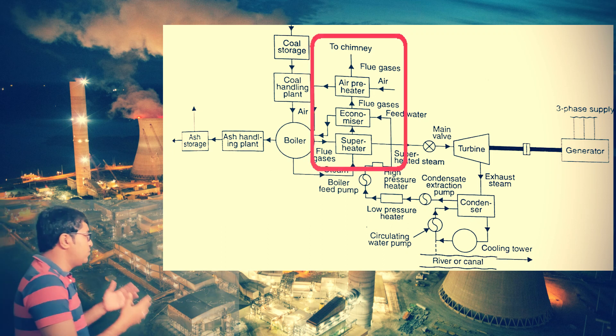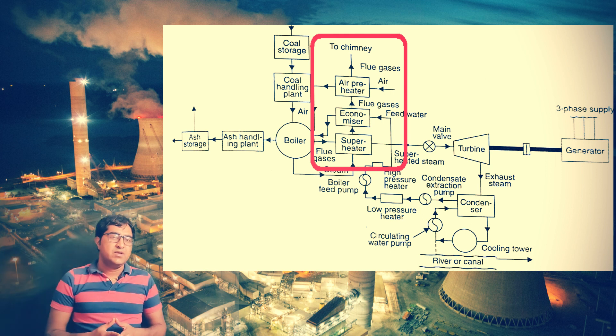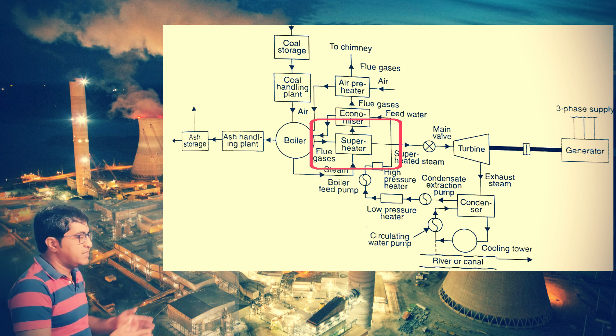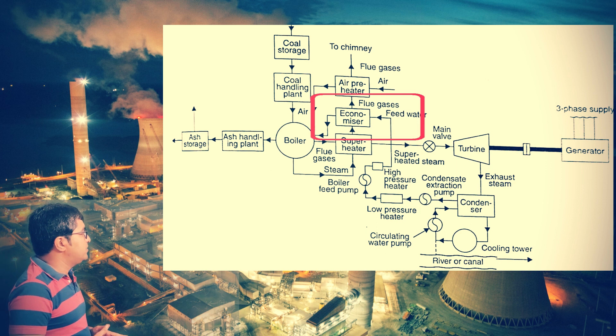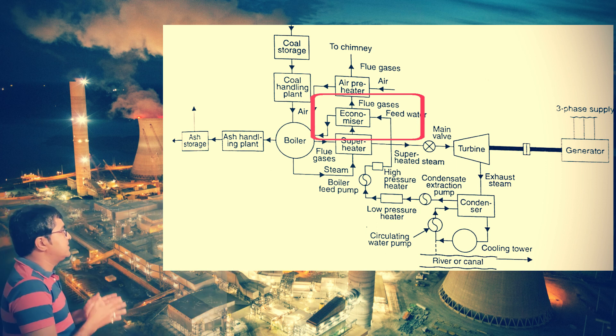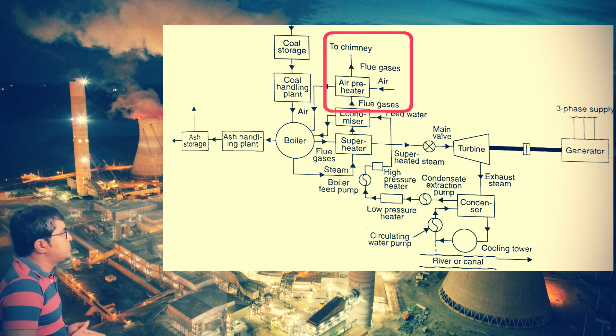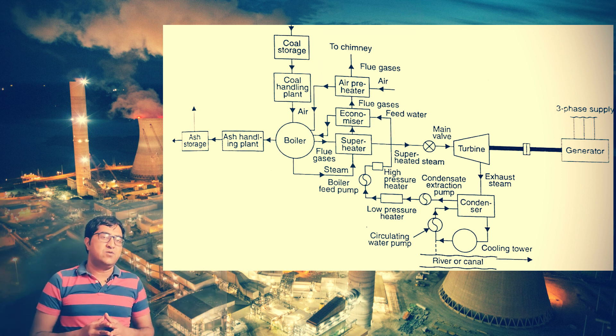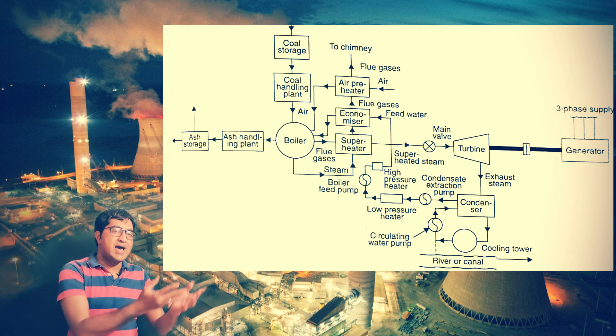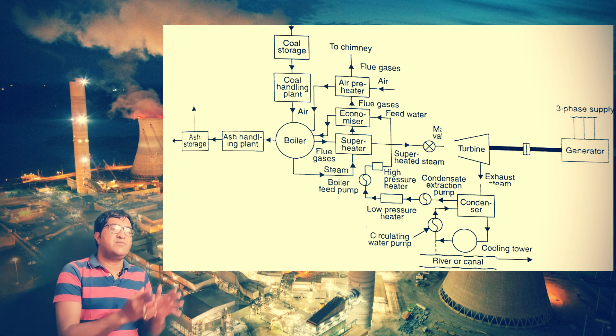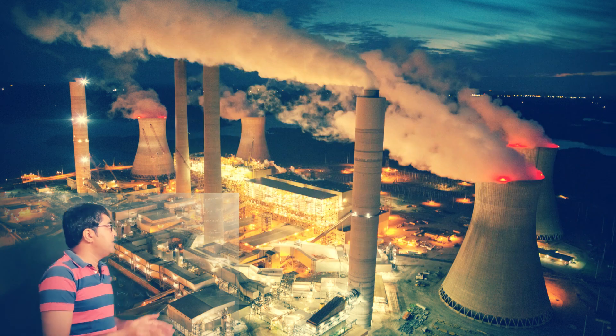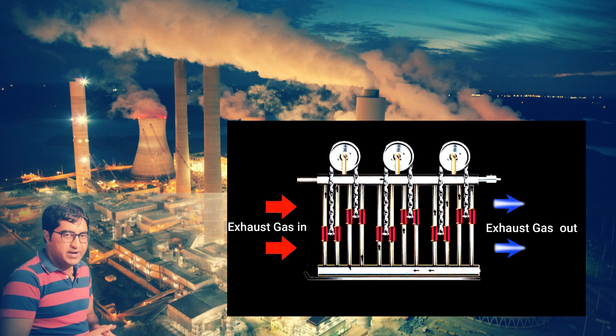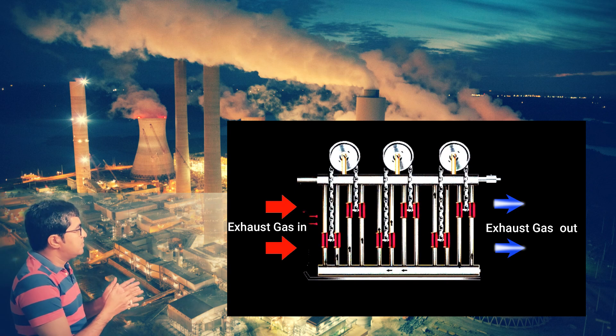The flue gases generated in the boiler pass through the superheater, where they transfer heat to generate superheated steam. Then the flue gases pass through the economizer, and finally through the air preheater before being exhausted to the atmosphere via the chimney. Since a small amount of energy is still available in the exhaust gases, exhausting them directly would be a wastage of thermal energy. Instead, they pass through heat exchangers — the economizer and air preheater — to recover that energy.